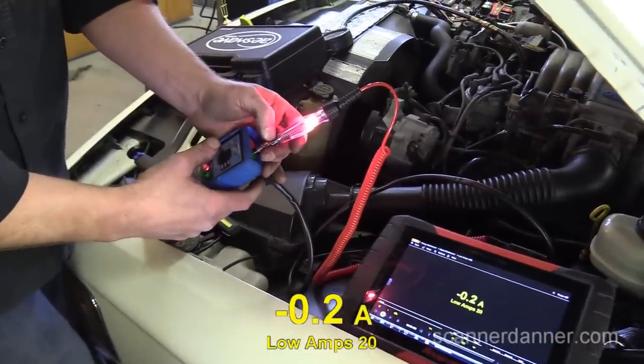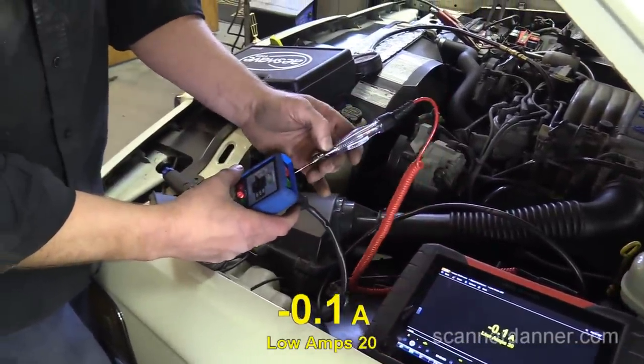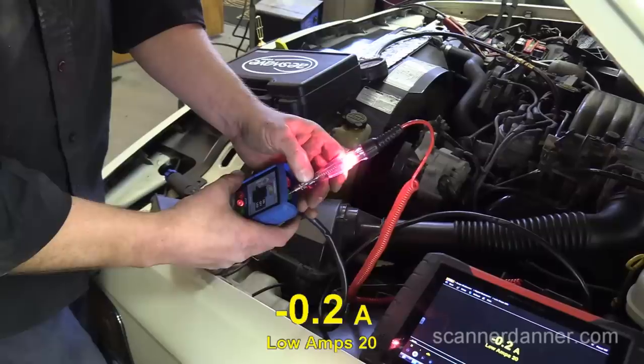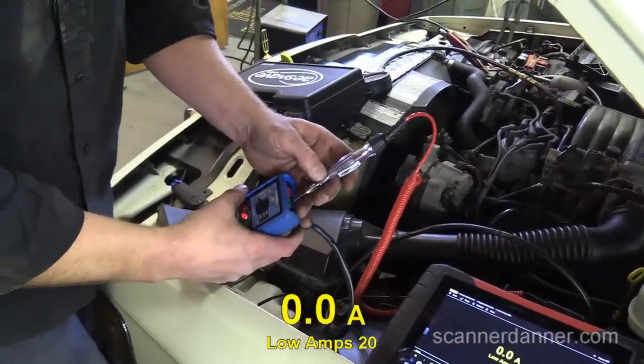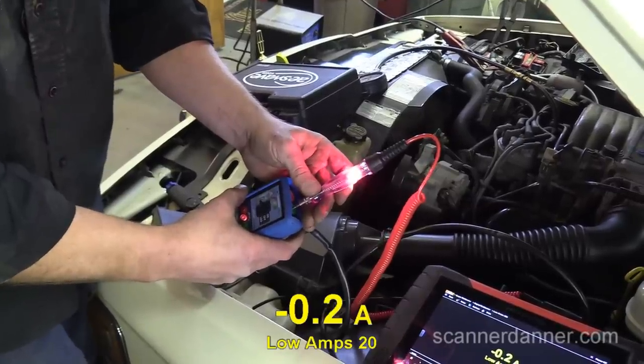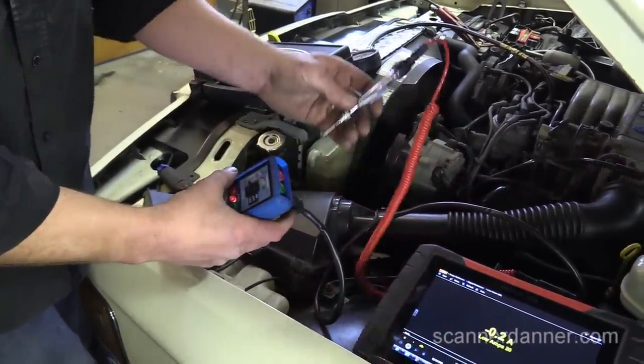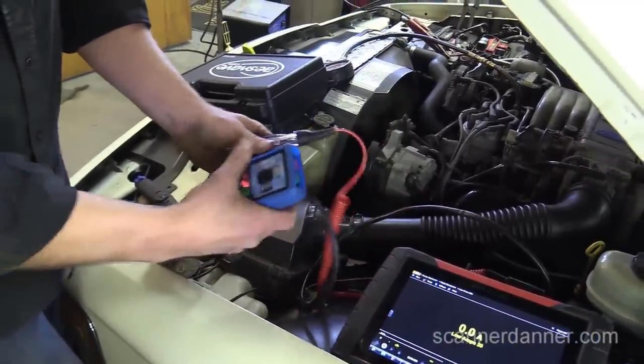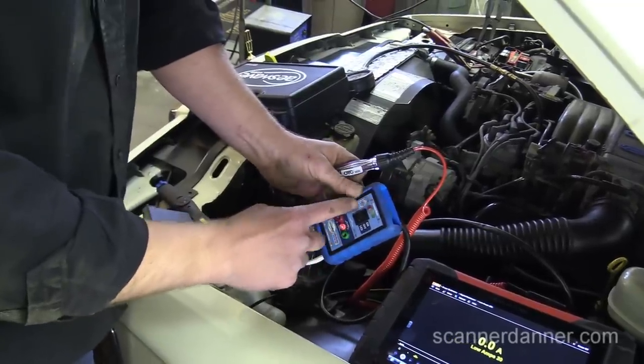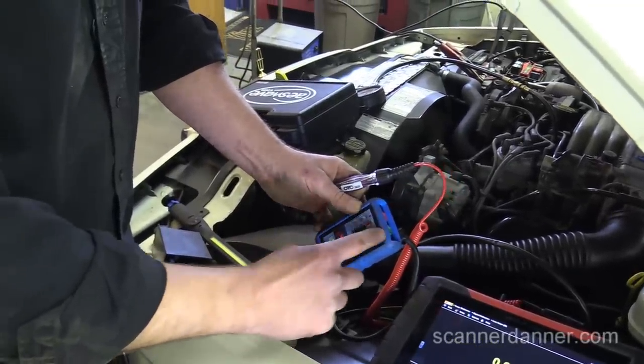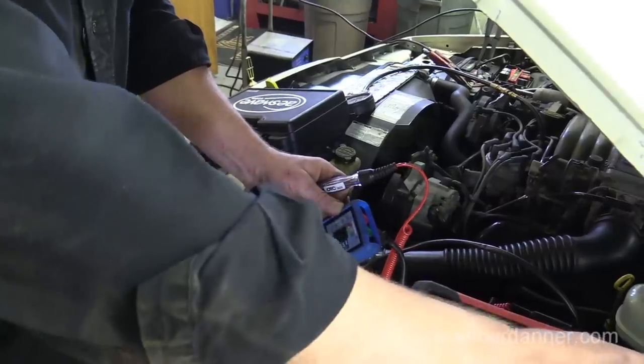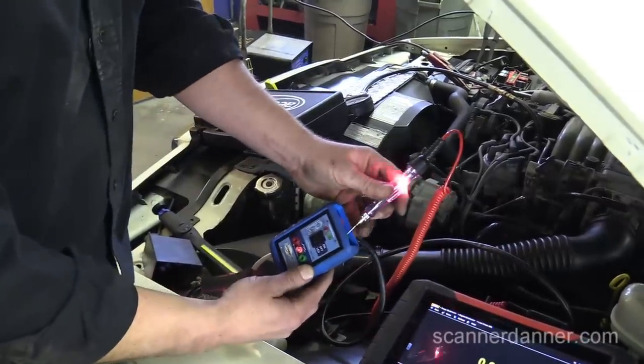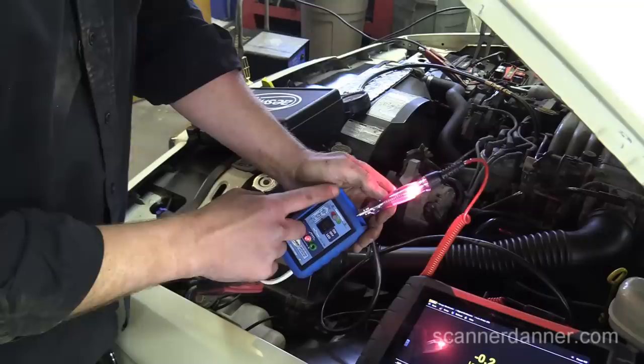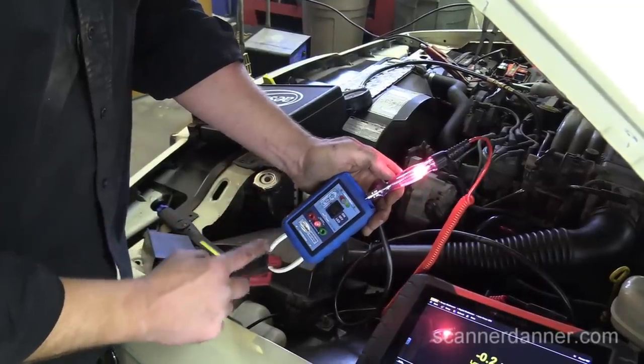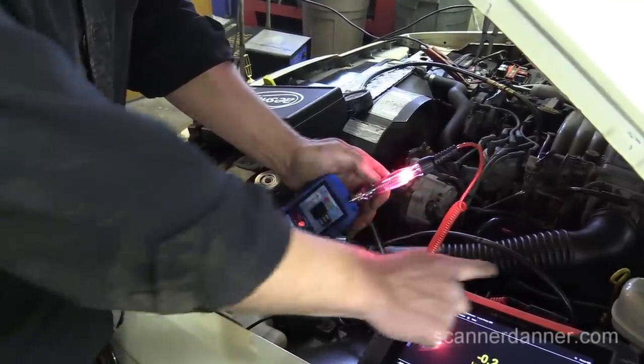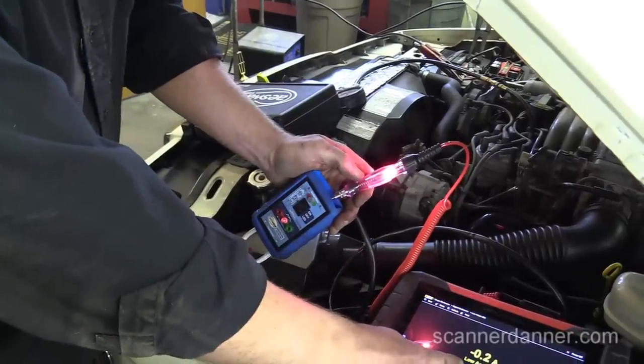You don't have to show that, that'll show up on there, but that's my test light. So when I'm under there checking my power feeds, what you're gonna see with the amperage is my test light amperage, that's what that is. Wait, how is that reading your test light? Look, power comes in here, loops through, comes out the green side, down to the pump. With my meter, my test light going to ground, it's looping from here, power, through here, and through my test light to ground there, and we're reading amperage.